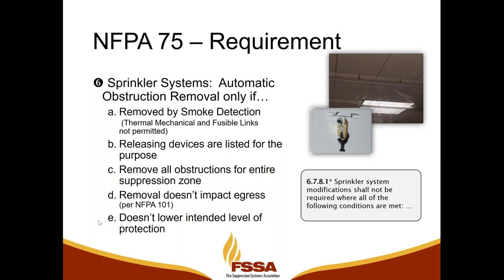And all the obstructions in the entire suppression zone, in the entire sprinkler zone or room, need to be removed. So it's not just removing the closest ones. We need to do the whole room at once. And the removal, as the obstruction material falls away, it can't impact the egress.